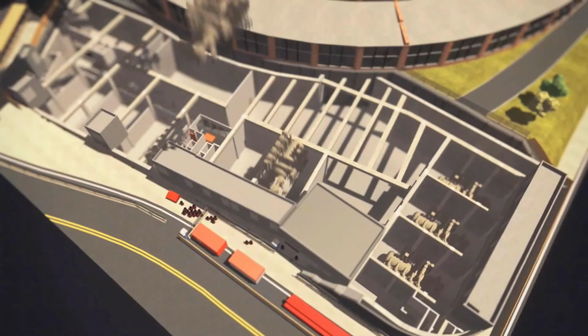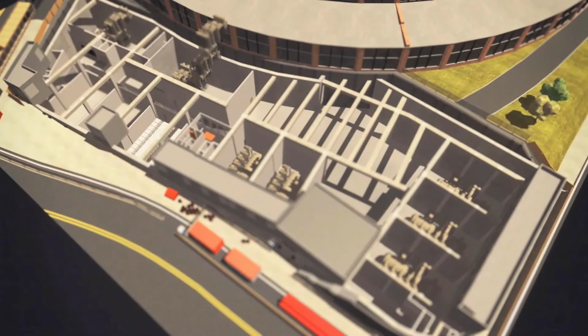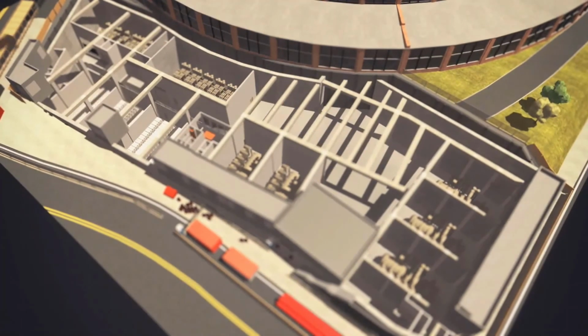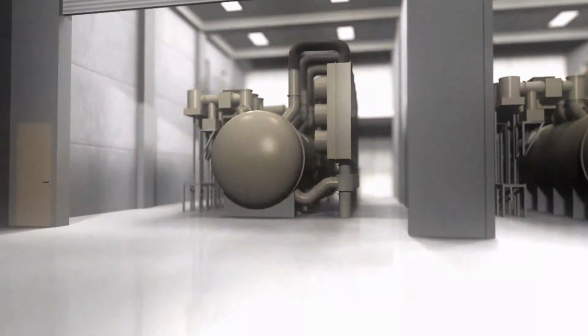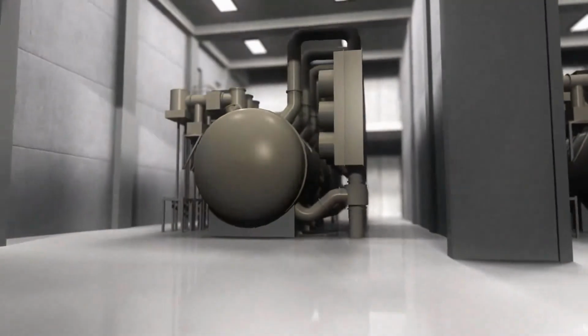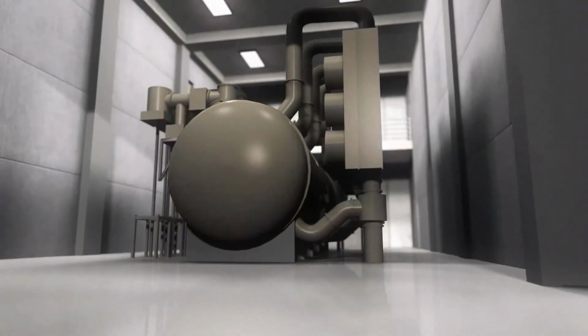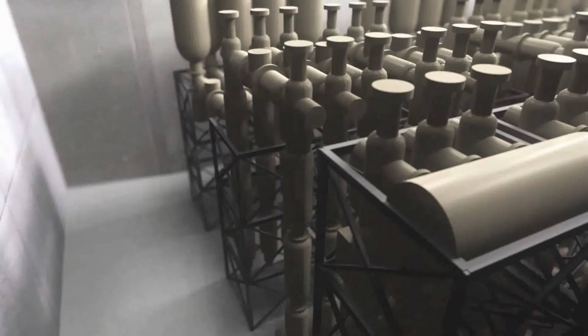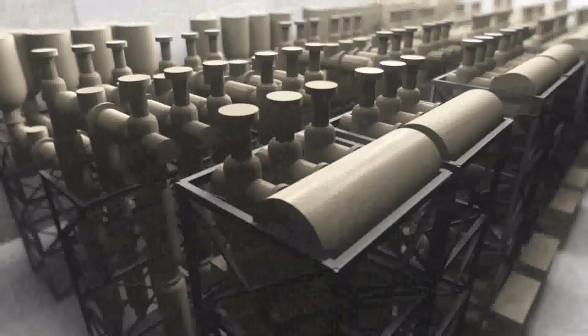When the structure is completed, all major equipment will be installed and connected. This includes gas-insulated transformers and high and medium voltage gas-insulated switchgear. Gas-insulated transformers are more compact than commonly used transformers insulated with oil.